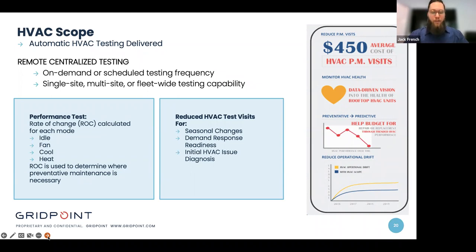And then from all of the data that we're collecting, we can, again, quantify, but not only quantify, we can qualify. We can add priority to which units had all-out failures, which units failed in only one mode. Are we testing only one mode? Which units failed in multiple stages? Things like that. So I kind of talked about some of this a little bit, but this is really beneficial during seasonal changes.